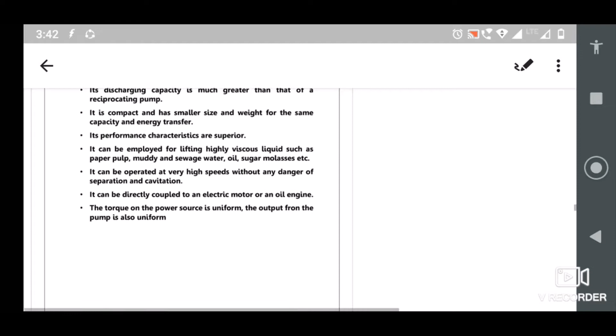And next we have priming. Initially, when you start your pump and switch on your motor, some amount of air leakage generally present in the pump would not allow your water to be lifted initially. So if you want to lift your water, you need to first remove the air which is generally sucked in or present. This operation we generally call priming: the operation of filling the suction pipe, the casing of the pump, and the portion of the delivery pipe completely with the liquid to be raised from an outside source before starting the pump, to remove any air, gases or vapor generally present in these parts, is called priming of the centrifugal pump.